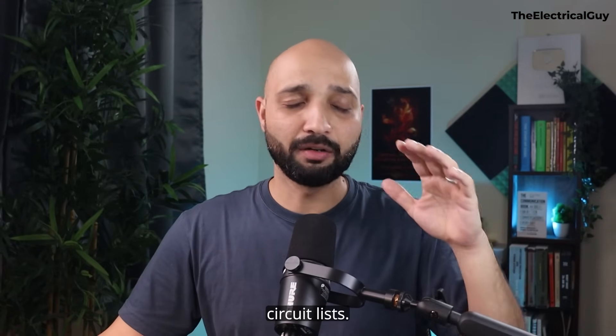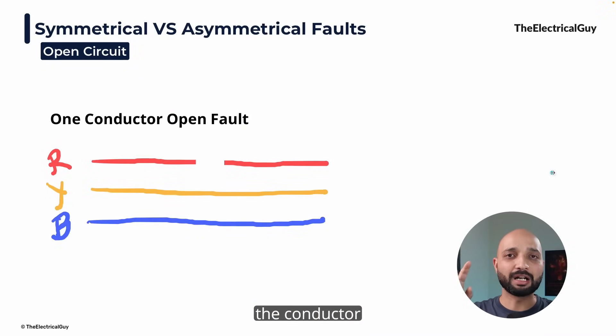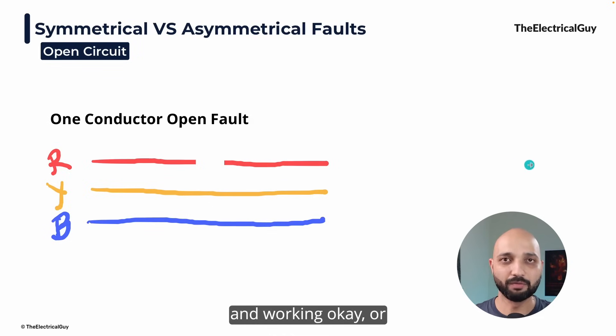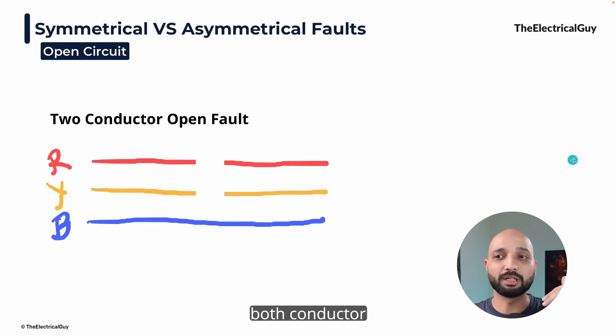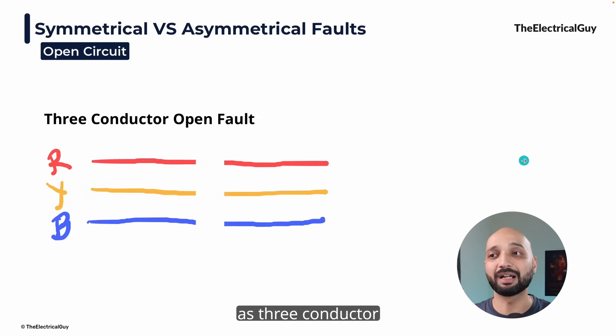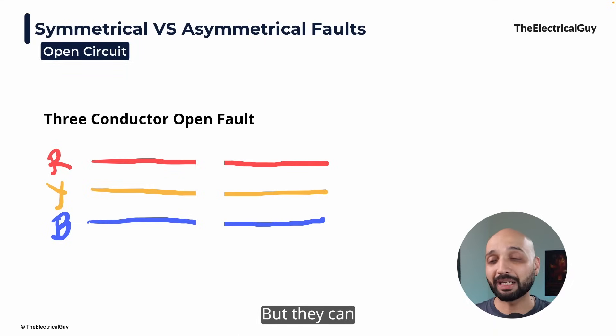Let us first start with the open circuit. In open circuit, the conductor will be broken down or cut for some reason and no current is flowing. There could be a one conductor open fault, where one conductor is open and the other two are perfectly fine. Or there is the possibility that two conductors from the three are broken down. Or maybe all three conductors are in the open circuit condition — that is called a three conductor open fault. These faults are not very severe in the power system and you will not see very serious consequences from them.